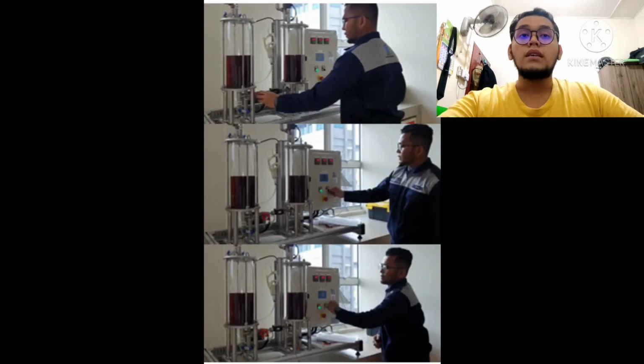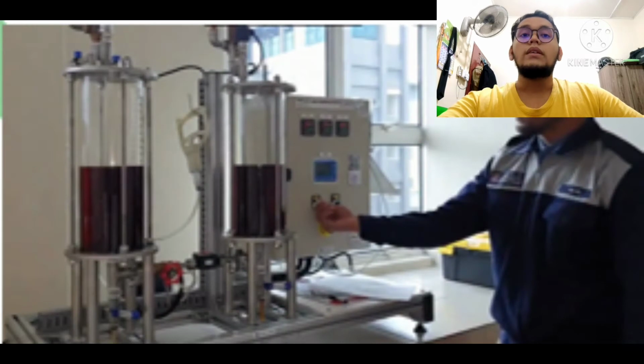But if the tanks are under vacuum, we need to open BV101 and GV101. Then switch on P101 until both tanks reach 0 bar. After that, we can switch off P101 and close all valves. Then after all this process is done, we can switch off the main power supply. For safety, before we turn on the power supply, we need to make sure that the equipment is properly connected and all the valves are closed.